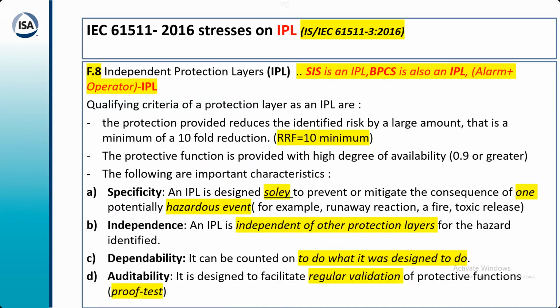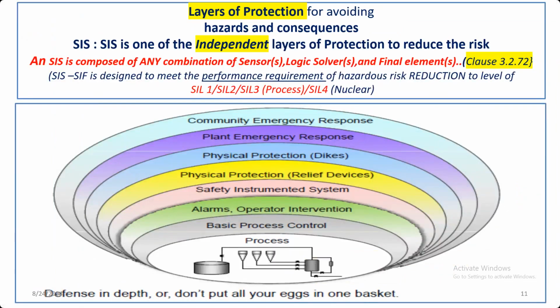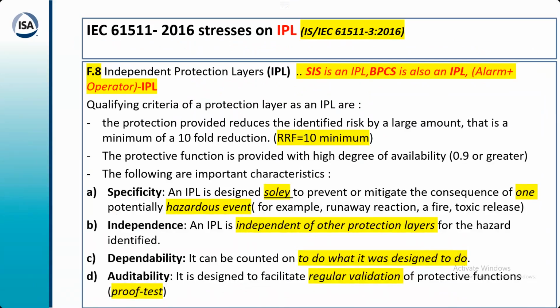Now, what is IPL? I mentioned to you that each of these layers has to be independent. So IPL means each layer has to work as an independent protection layer, not IPL cricket. Here SIS is an independent protection layer. BPCS is also an independent protection layer, and alarm and operator is also an independent protection layer. But here the standard defines that an IPL should give a minimum risk reduction by a factor of 10.